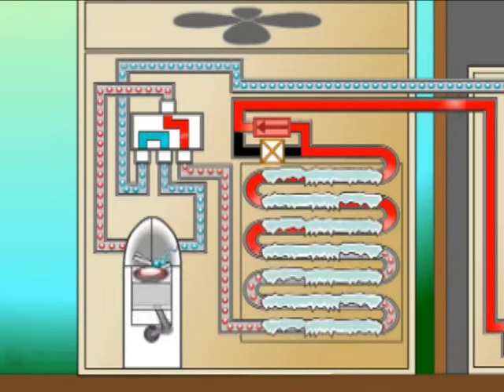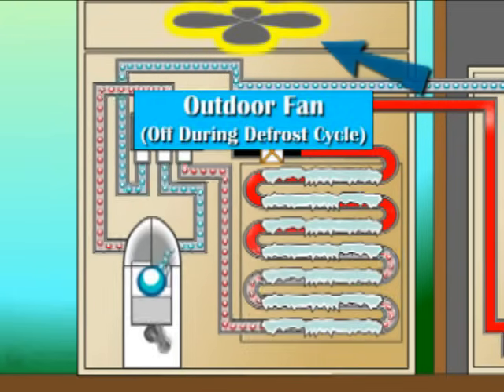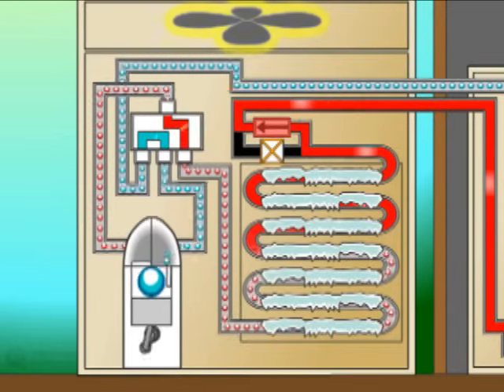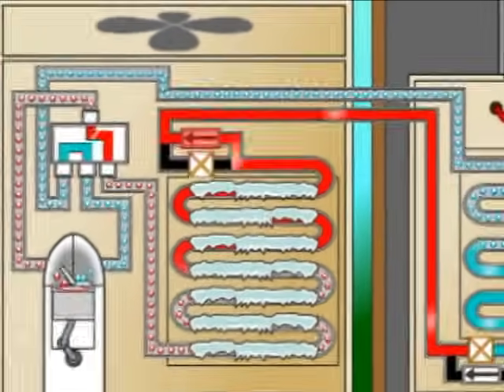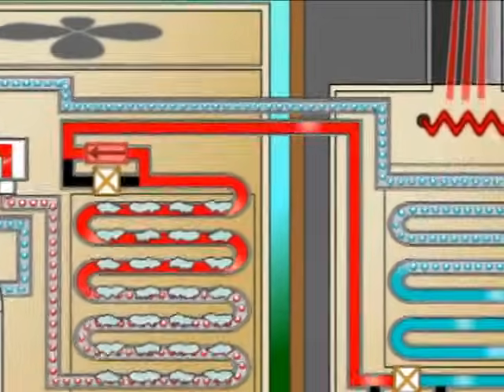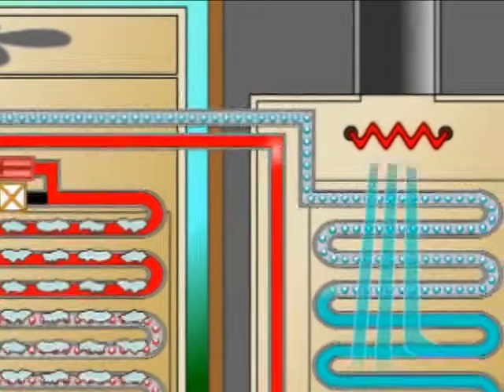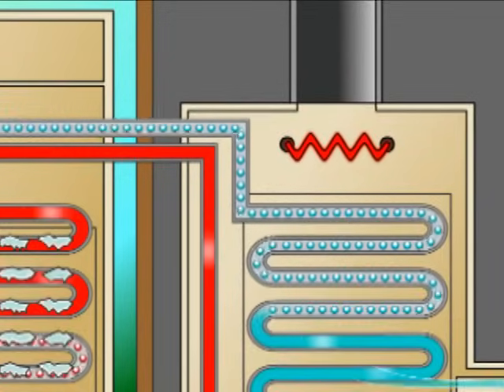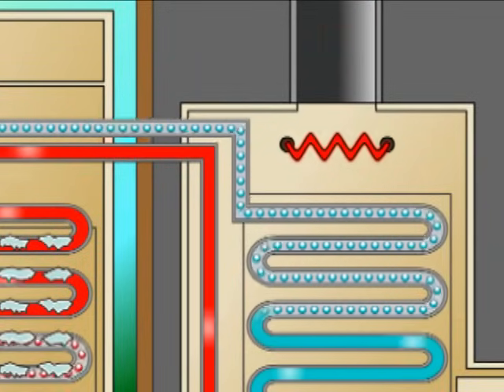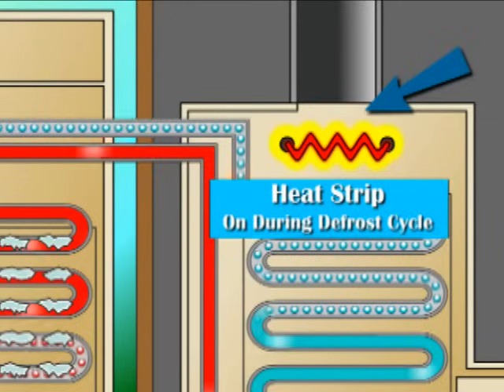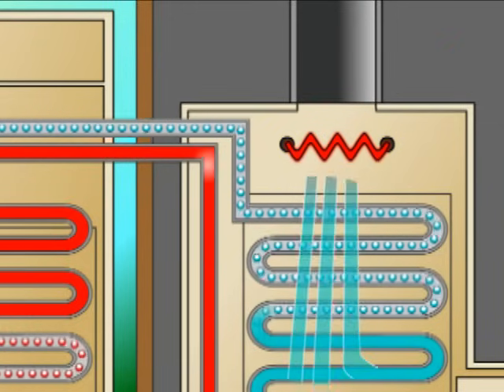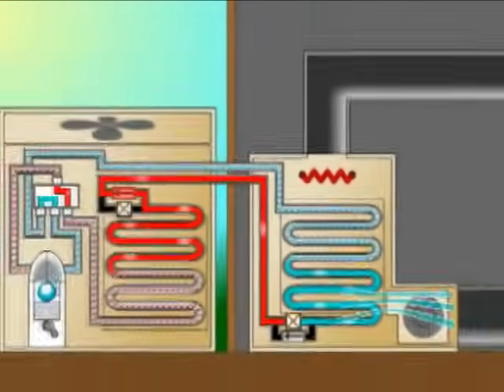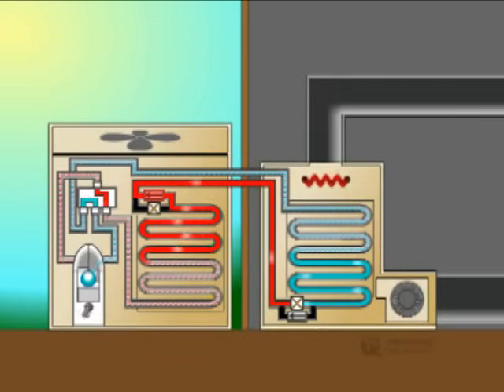To speed this process up, outdoor fan operation is terminated throughout the defrost cycle. Also notice that the indoor air stream, now being robbed of its heat, becomes very cold, which is not a desirable condition during winter. To compensate for this condition, the auxiliary heat is activated for the duration of the defrost cycle. After a few minutes, the outdoor coil is frost free and the defrost cycle is terminated.